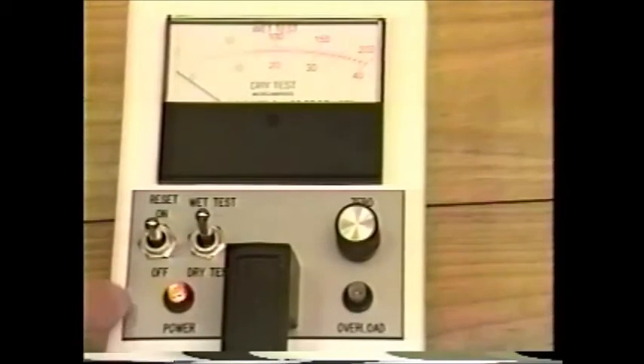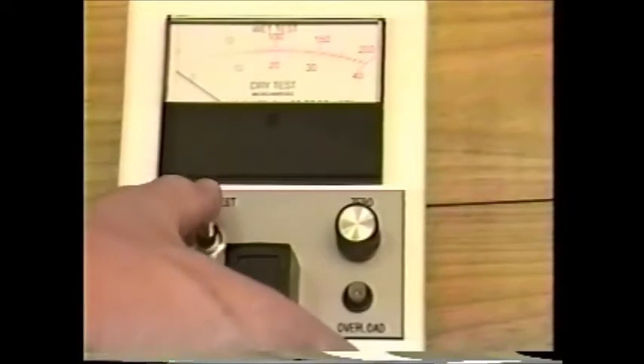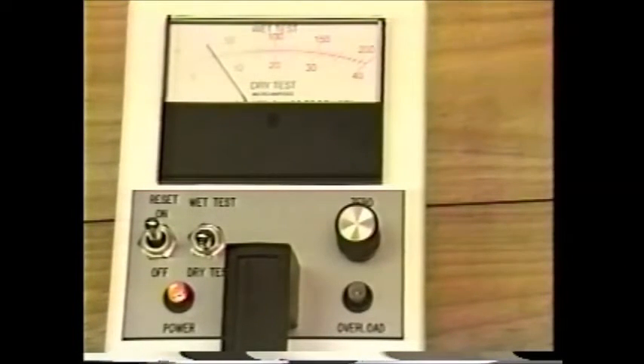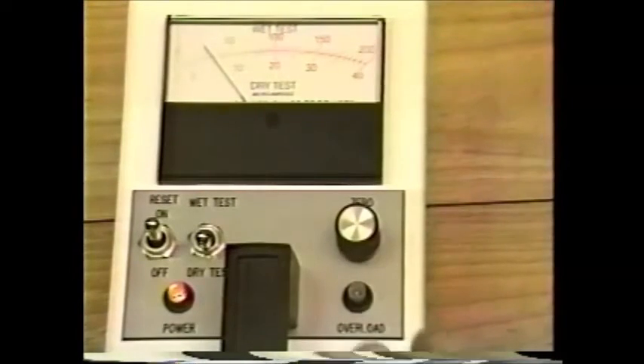The tester allows the user to select between two test modes. Both the wet test required by OSHA and a more sensitive dry test can be selected. The full-scale deflection for the dry scale is 40 microamps. The full-scale deflection for the wet scale is 200 microamps.